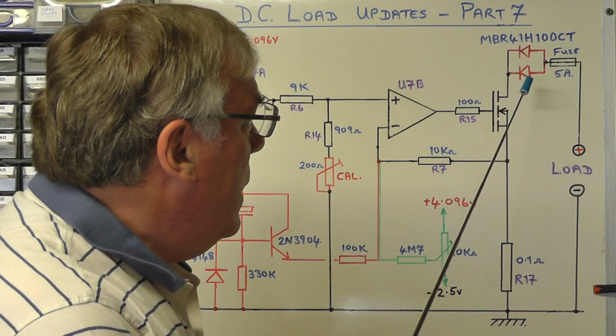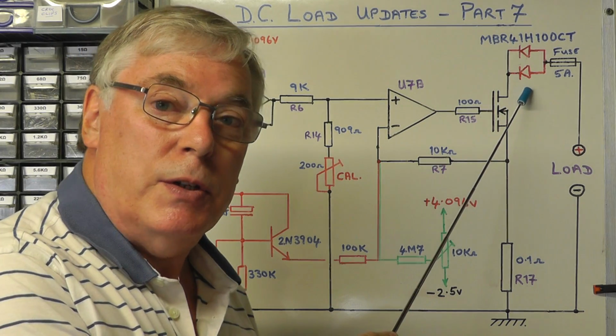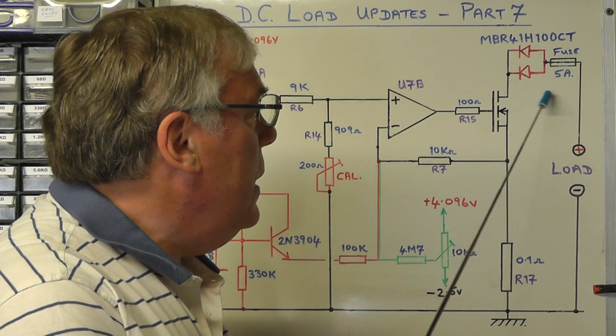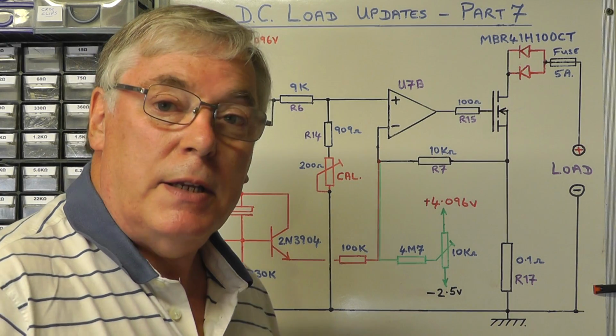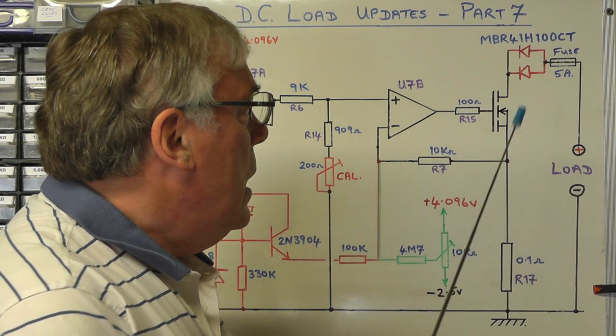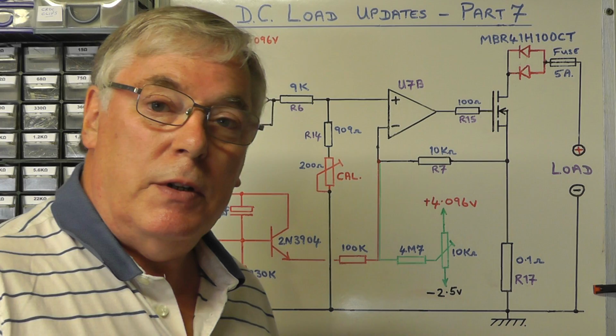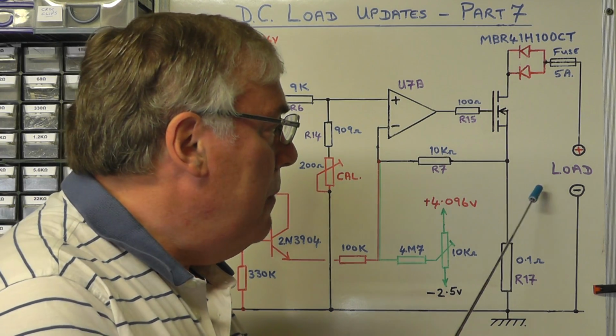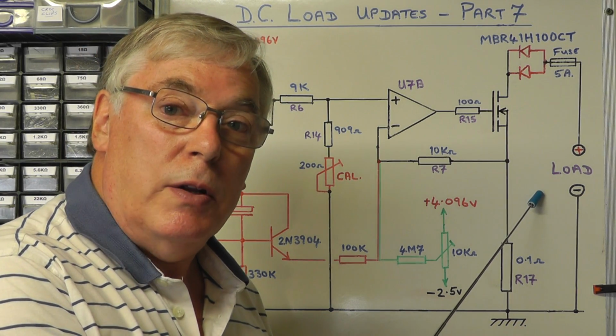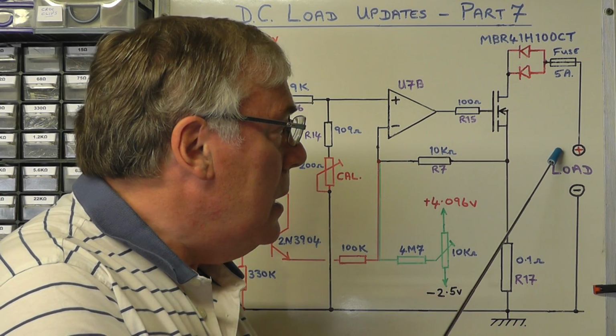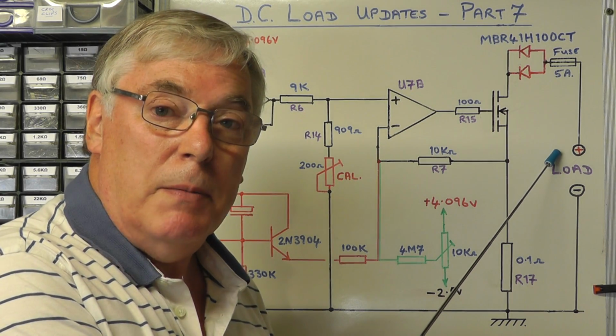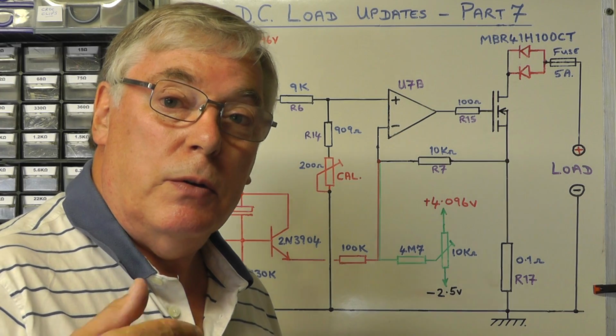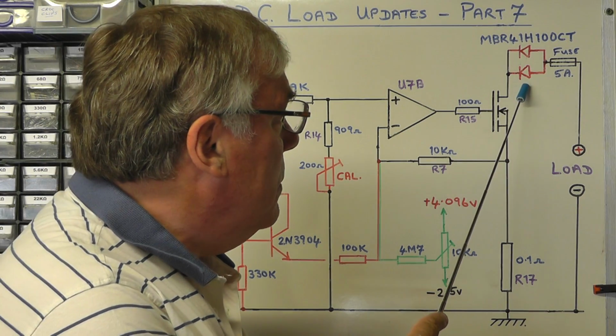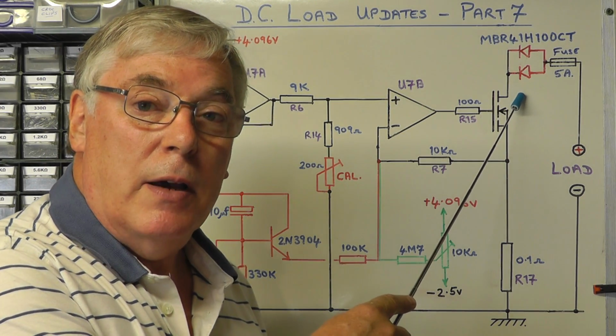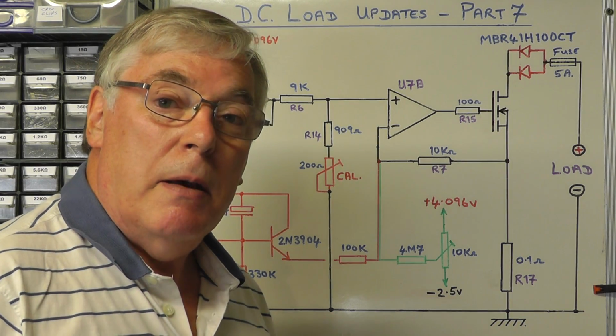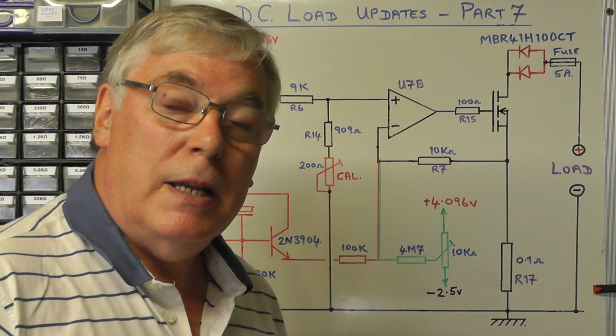So if we take the first one, where we've got two diodes on the output of the DC load in series with the fuse - the reason behind that is I wanted to give a degree of protection in the event you applied a load in reverse. So if you applied the negative of the load onto the positive terminal, in order to prevent any damage we can put some blocking diodes in there, DC blocking diodes, and for that I've used a dual power diode which comes in a TO220 package.